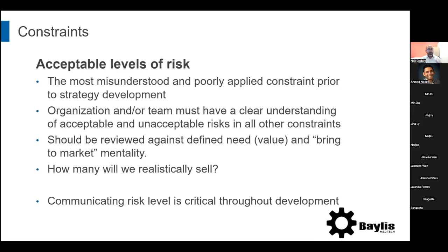If the regulatory requirement is that it has to pass at 10 newtons and you get to 10, but if you test a failure, they all fail at 11, you would feel a lot different about that than if they're all failing at 100, right? And you need to know these things rather than just saying, hey, everything looks good, fingers crossed.